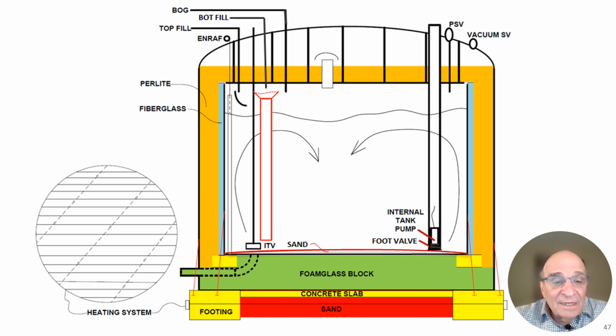But let's say this is an older system, and older systems had on-off thermostats. They come on, they come off. Well, what happens to the wire? The wire stretches and it shrinks, stretches and it shrinks. Why? Because it's hot and then it's cold, hot and it's cold. And that causes chafing, and it can cause the wiring to short out. So a lot of these systems have been converted to modulating voltage instead of on-off thermostats. And modulating voltage limits the amount of chafing because it limits the amount of high temperature, cold temperature, high temperature, cold temperature.